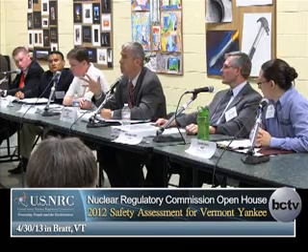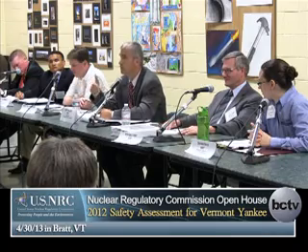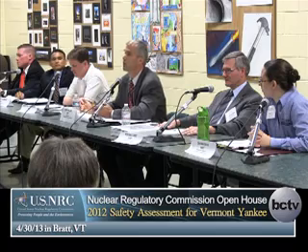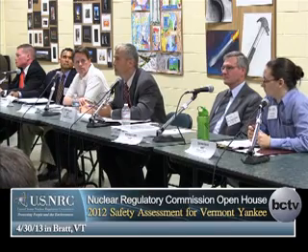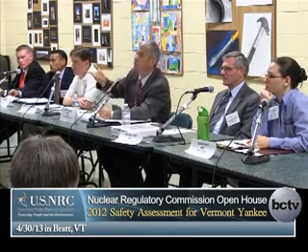The other thing that was reported to the NRC during this outage, and you asked about 2012, but just so you're not surprised, during this last refueling outage, there was an issue where water went through a conduit cable, and we don't have the final results on our inspection on that. We're still looking at that and doing a risk analysis on what that could have caused in a flood. But that will be reported out on one of our subsequent reports. It just wasn't in the 2012 reports issued.